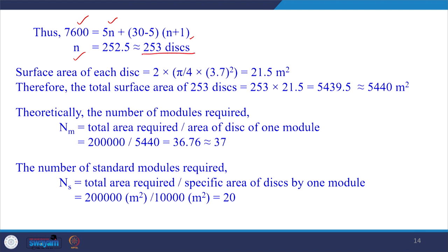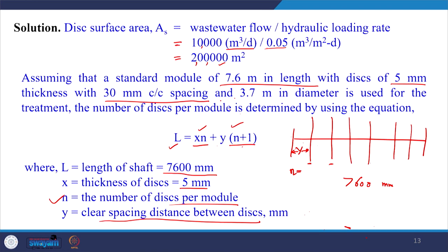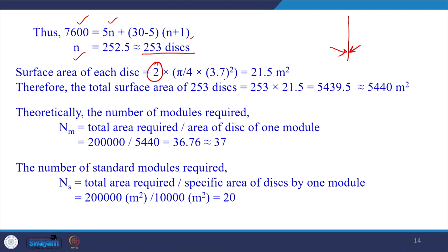The surface area of each disc is calculated as 2 × (π/4) × 3.7² = 21.5 m² (both surfaces counted). Multiplying by 253 discs gives approximately 5,440 m² of disc area per module.